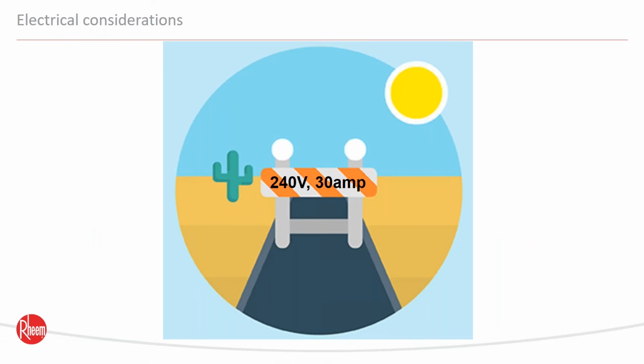So again, the biggest hurdle you guys are going to run into is the electrical demand for these. It's a traditional electric water heater. The reason you need 240 volts, or 208 to 240 volt 30 amp, is because of the elements - they're 4,500 watt elements, so UL requires 80% of that circuit, with 20% not used during that time, so it doesn't create a toaster effect inside the walls. That's going to be the biggest hurdle for you. We make a 240 volt 15 amp model, so our elements are 2,250 watts instead of 4,500 watts. That's also available for you as a contractor - it's basically a single pole 240 volt instead of a double pole, if you're really panel challenged in getting this into the electrical panel.